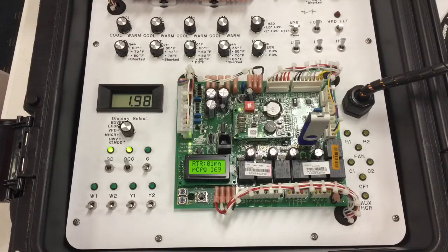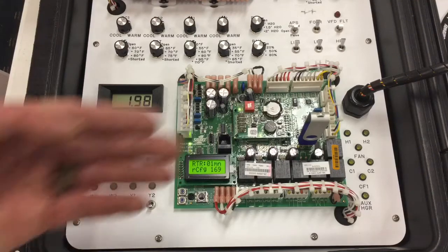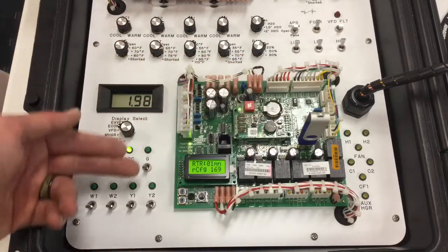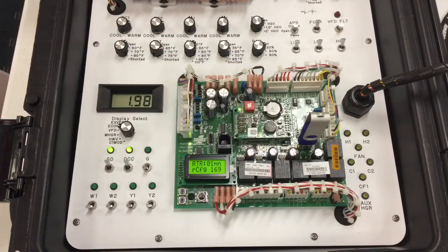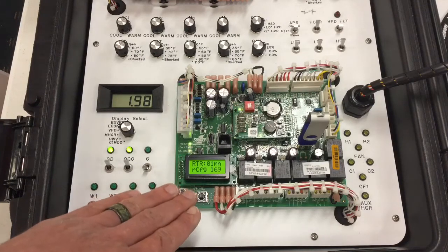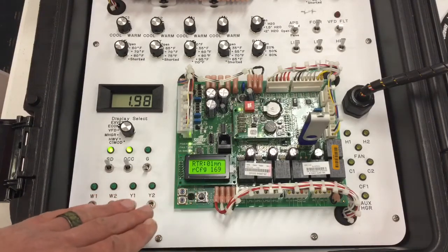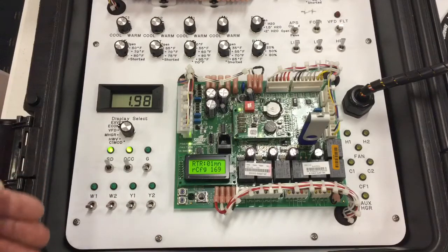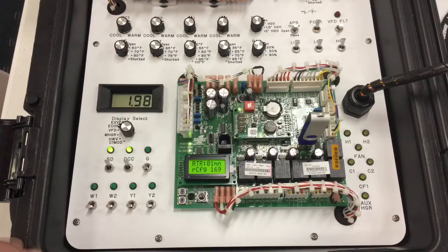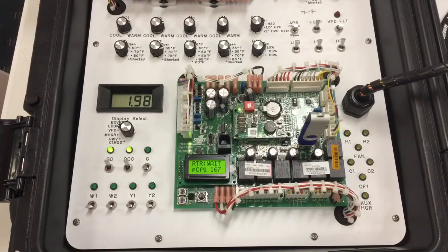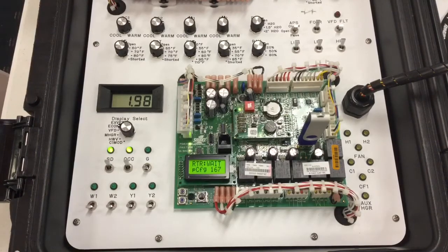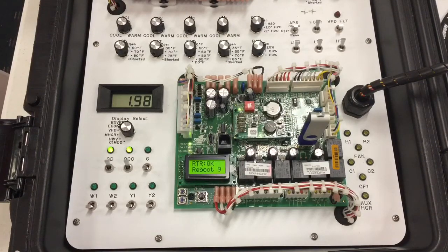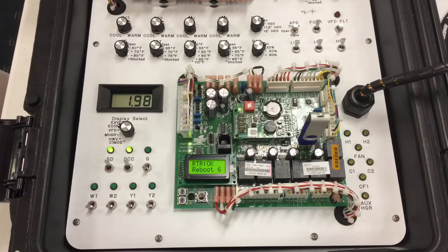At this point, the restore is happening, and I'm extracting the files from this USB flash drive onto this control board. At the end of this process, once these 169 files have been transferred successfully, the unit will shut down and do a reboot feature. The reboot will count down from 10 down to zero. At that point, it will initiate another 120 second countdown and reboot the controller.